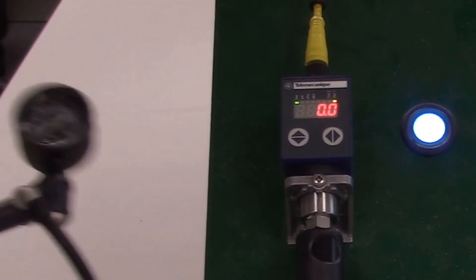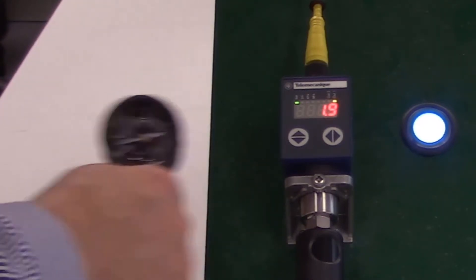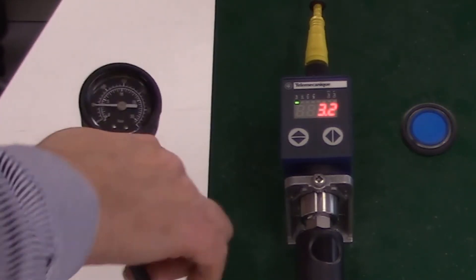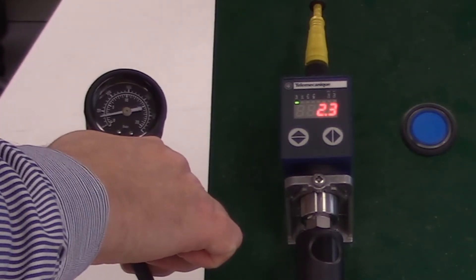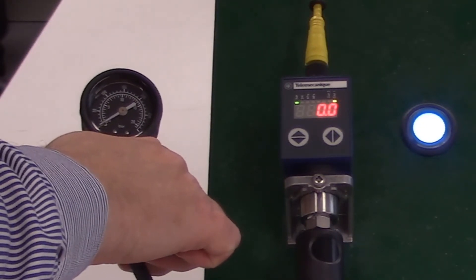In our XMLR pressure switch, set point 1 is set to 3.5 bar and the reset pressure to 1.5 bar. So when we pressurise up above 3.5 bar the light turns off, and as we decrease the pressure the light will turn back on at 1.5 bar as shown. Thanks for watching.